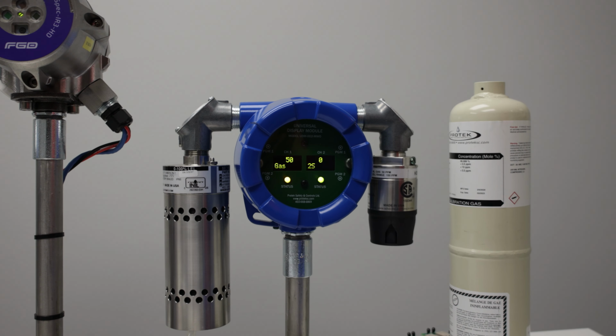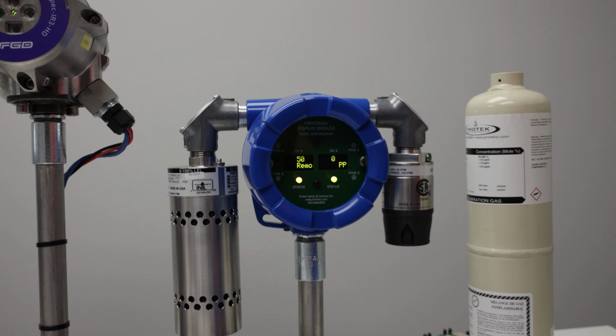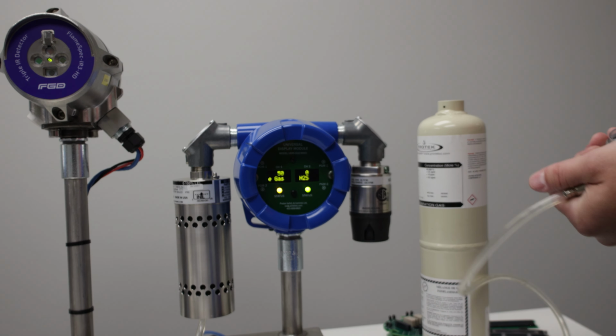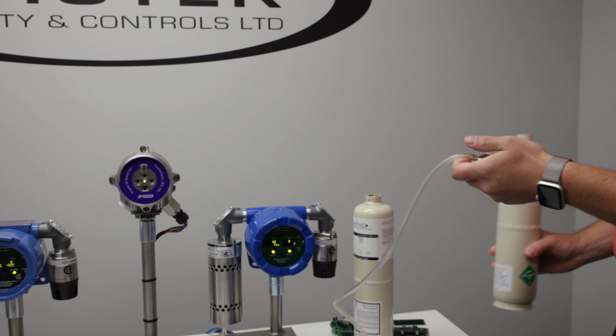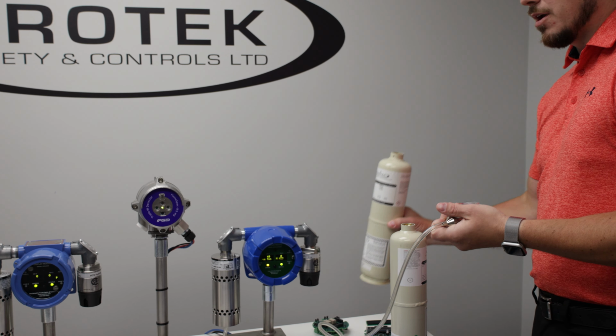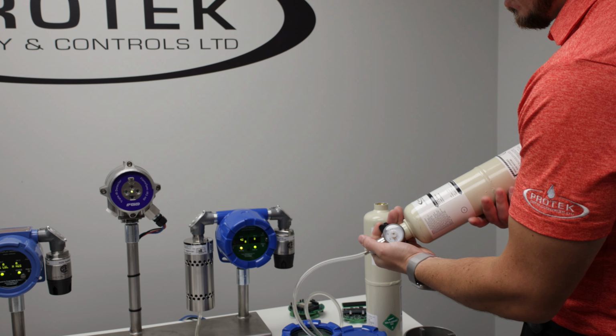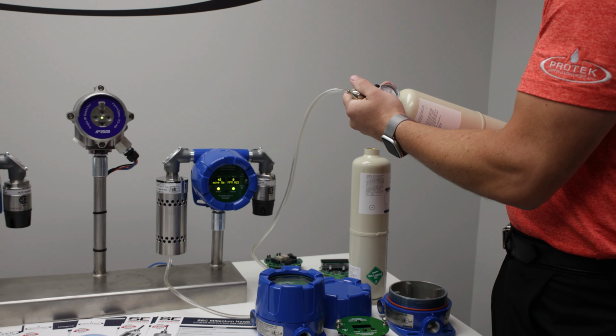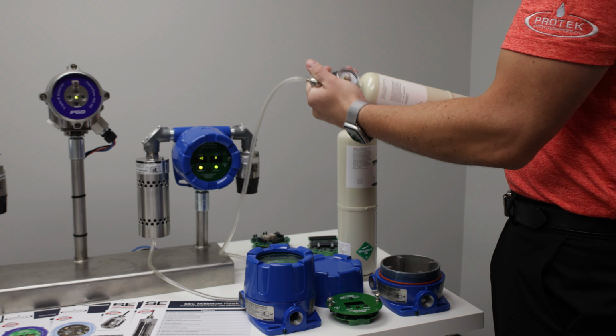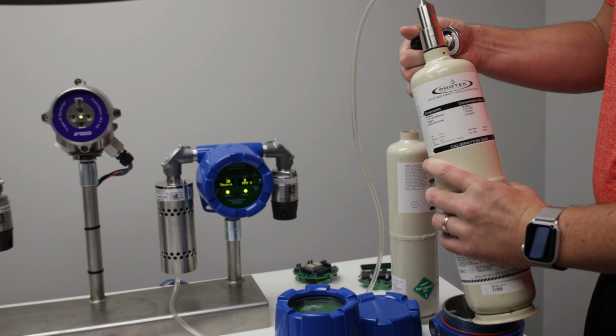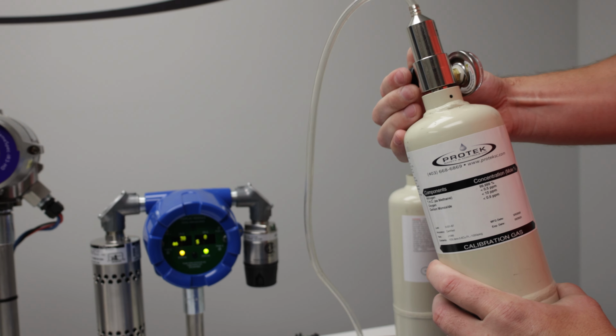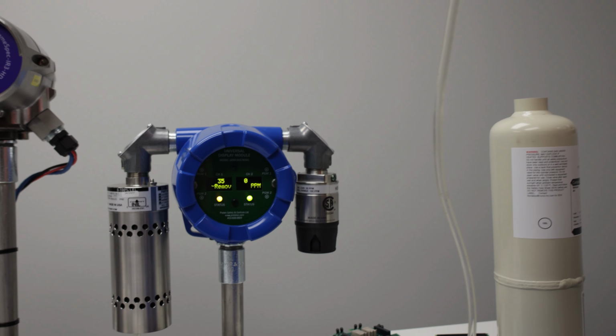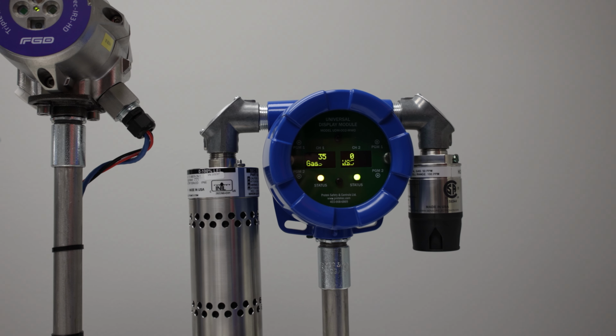At this time we're going to remove our cal gas, and we're actually going to connect to the fresh air, and we're going to purge the sensor, get rid of all that gas out of the sensor, bringing it back down to 0. This way if there is gas in the background, we'll be able to see it. So applying our 0 cal gas, which can be supplied by Protek. You'll see it's going to come down as we purge it with fresh air.